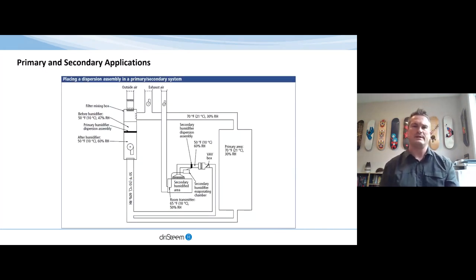So how can we do this for a space? Well, there's one method, primary and secondary applications, where we look at if there's a central air system or air handlers for a particular building, and a baseline is added for the predominant conditions of the space. That then goes through the distribution network for the building for primary areas. If we have secondary areas that are being controlled through temperature with VAV boxes, we can then add secondary dispersion after that, whether that's a localized generator or part of a pressurized steam network. Then we can individually control the secondary spaces.